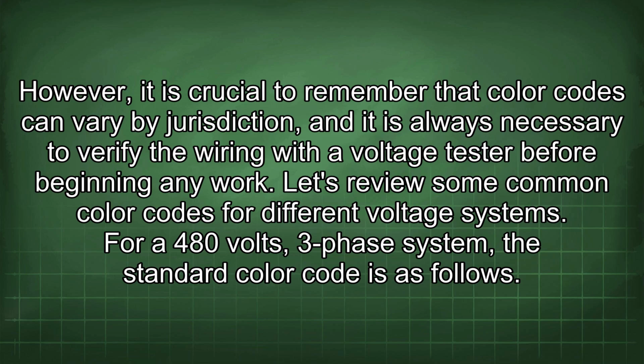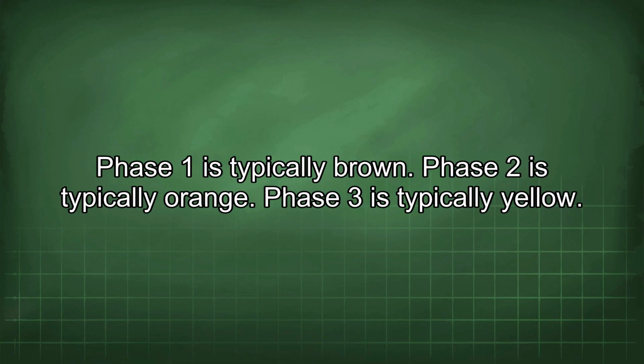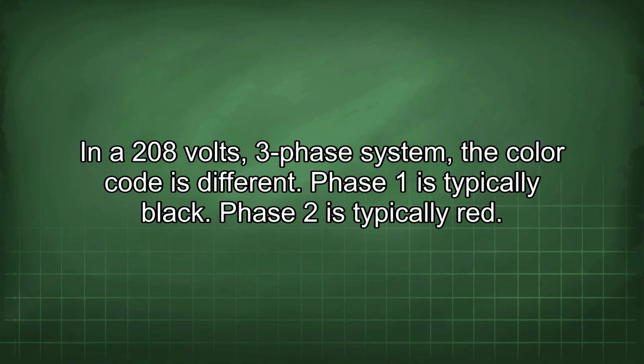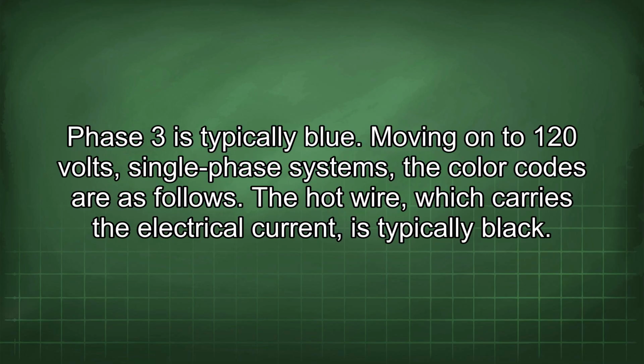Let's review some common color codes for different voltage systems. For a 480 volts, 3-phase system, the standard color code is as follows. Phase 1 is typically brown. Phase 2 is typically orange. Phase 3 is typically yellow. In a 208 volts, 3-phase system, the color code is different. Phase 1 is typically black. Phase 2 is typically red. Phase 3 is typically blue.